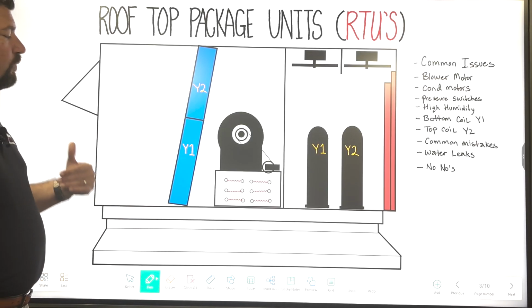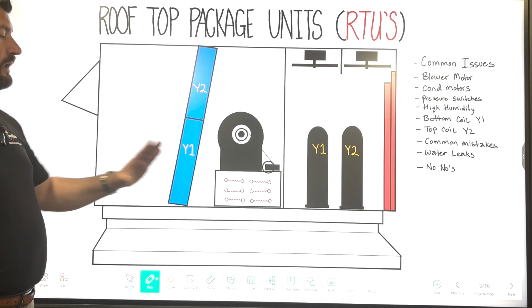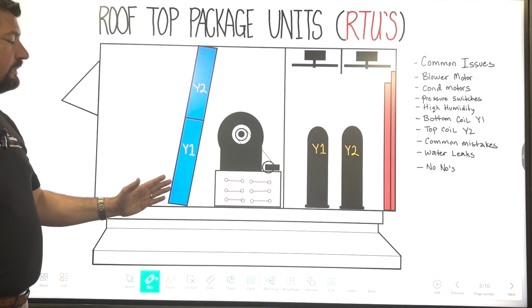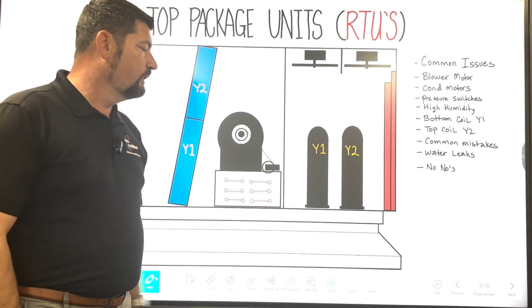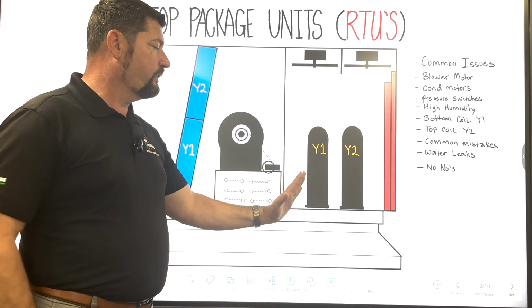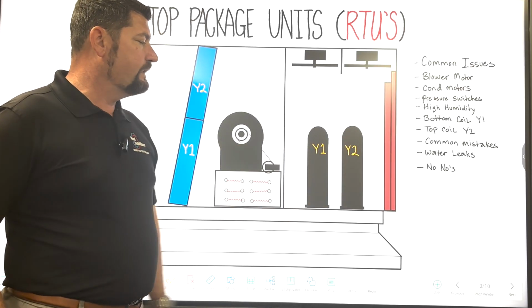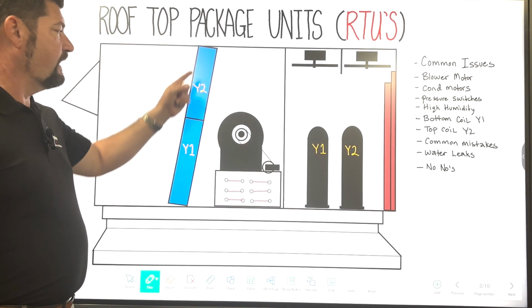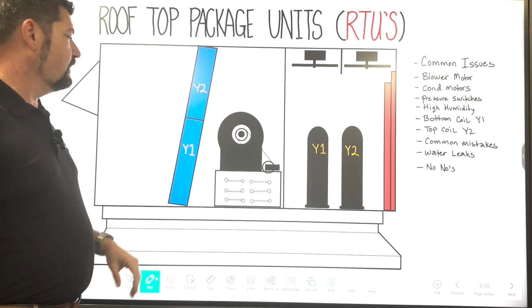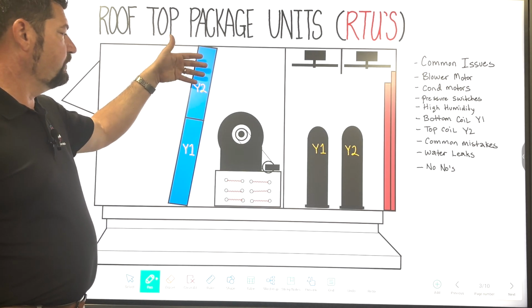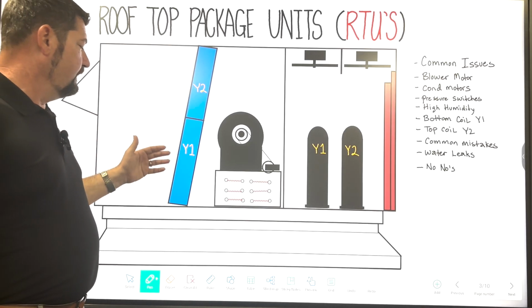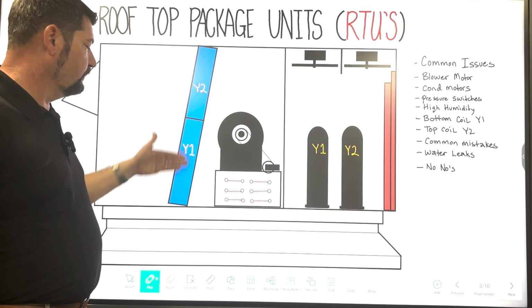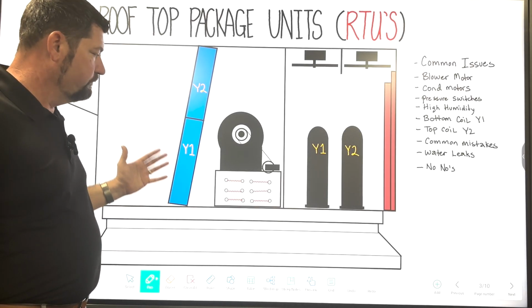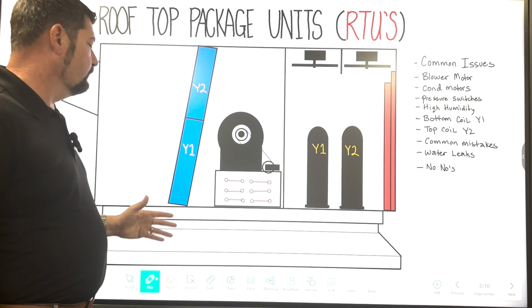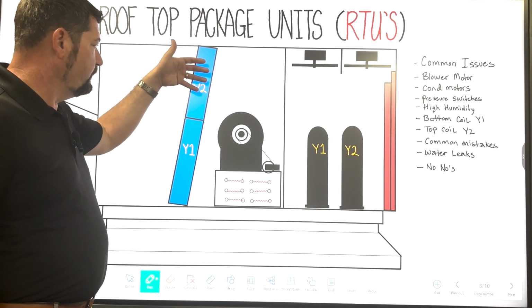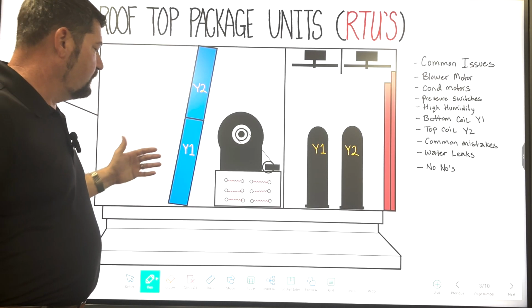However, if you wind up having a dry condition outside and you were to, say, lose Y1 compressor, circuit 1, and that compressor's off, and the only other thing you can do is just wire the system to run Y2, well, you're running the top side of that evaporator coil, and you're not running the bottom side of that coil. So what happens is all the moisture that is being collected up on this coil will now run down, and this coil is no longer cold here because the circuit is not moving any heat. There's no BTUs on this bottom of the coil. So now that water that's coming off of this coil out of the air is running down and going back into the air.